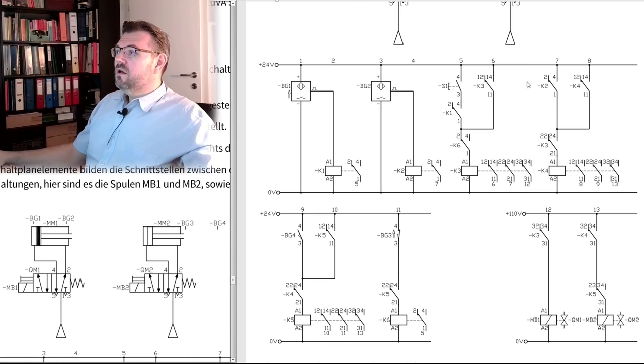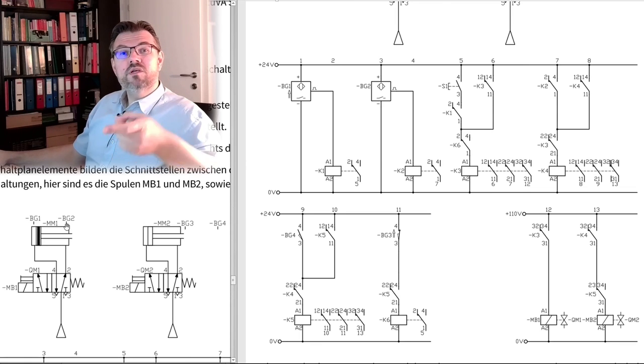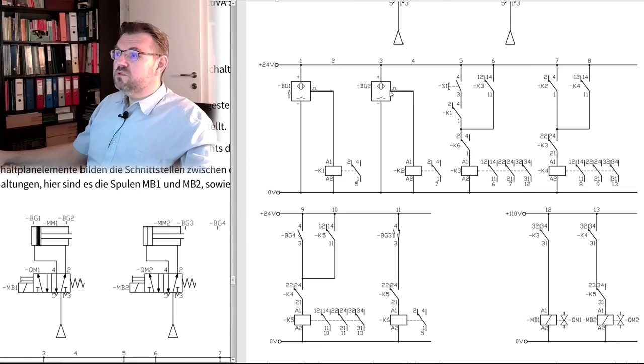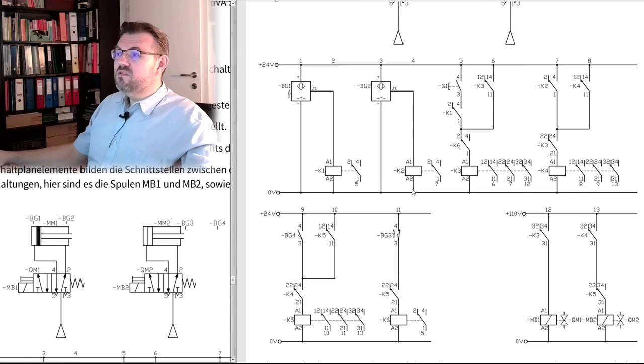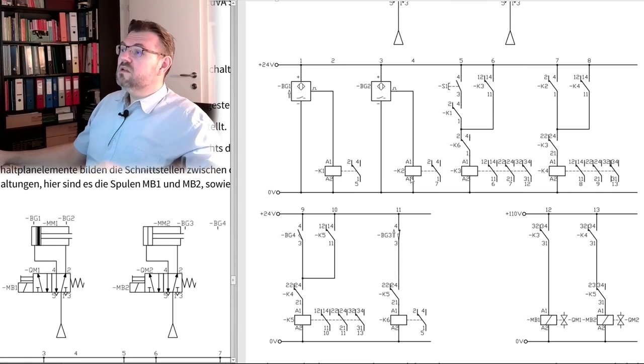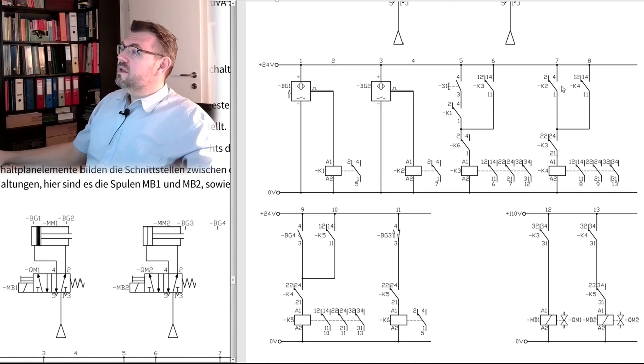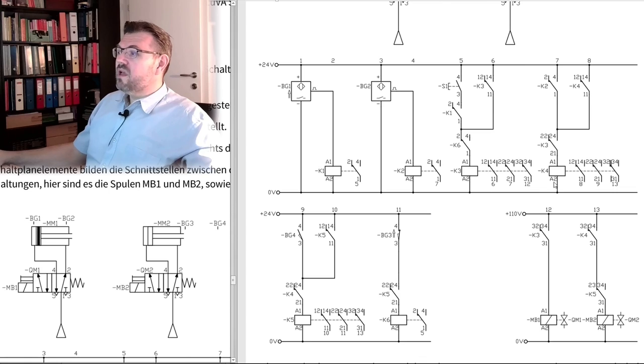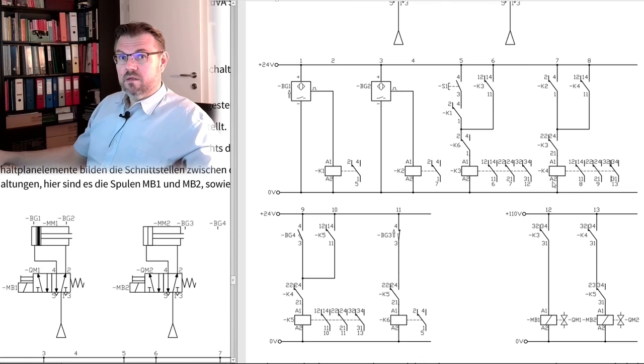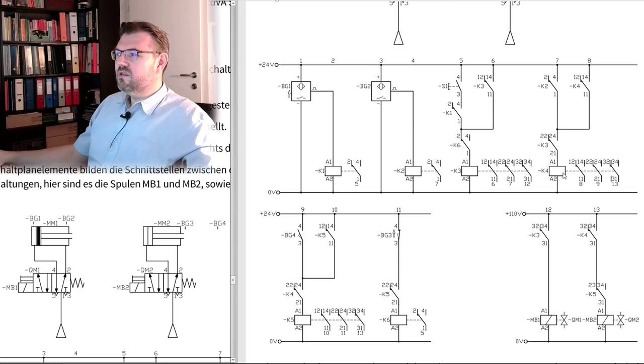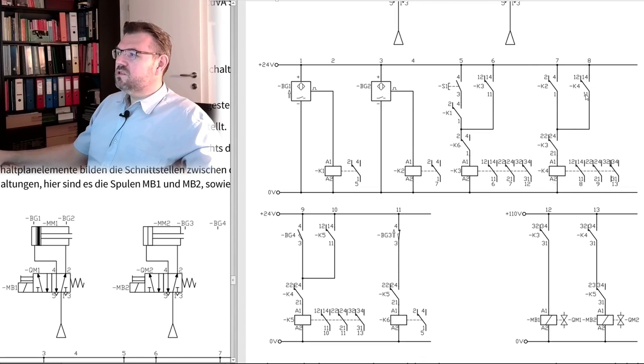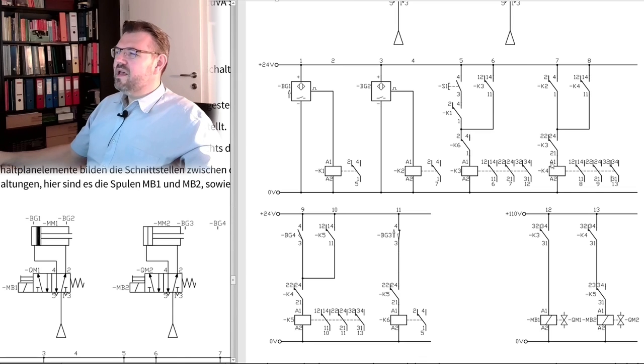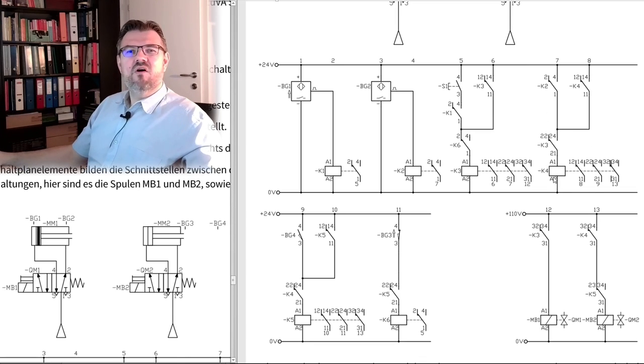And however, what is then happening, then at some point in time, BG2 is activated. If BG2 is activated, K2 is activated. So K2 is activated, if K2 is activated, and K3 is still activated, then K4 is also activated. K4 is activated, and here we have again the storage. K4 is now holding itself. As long as K3 is on, K4 will stay on.